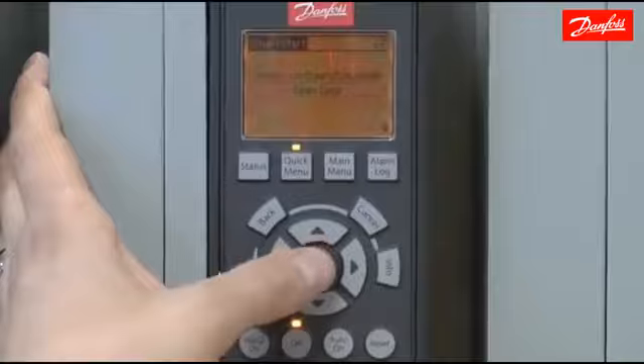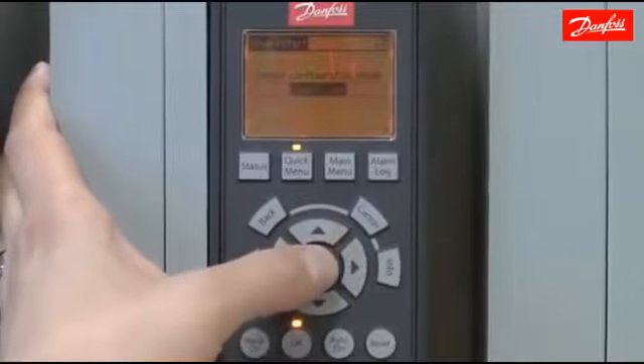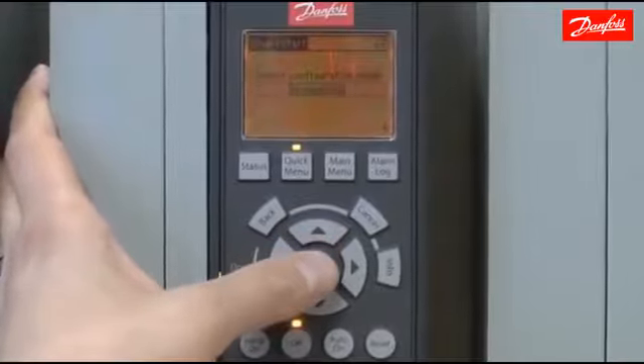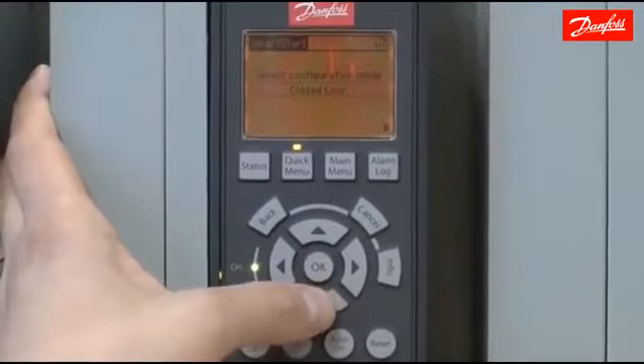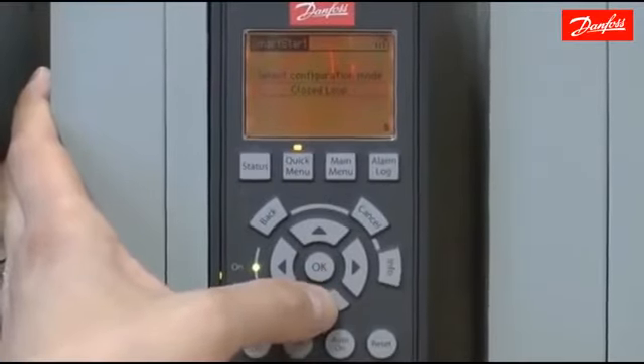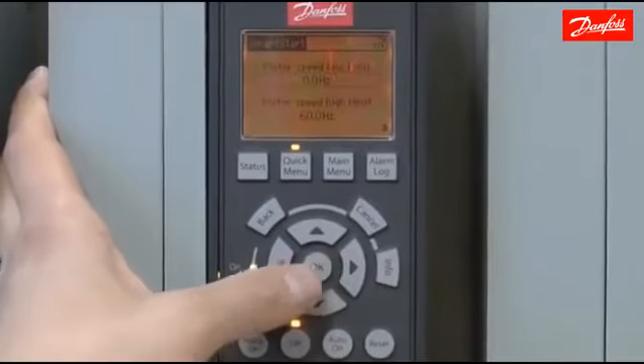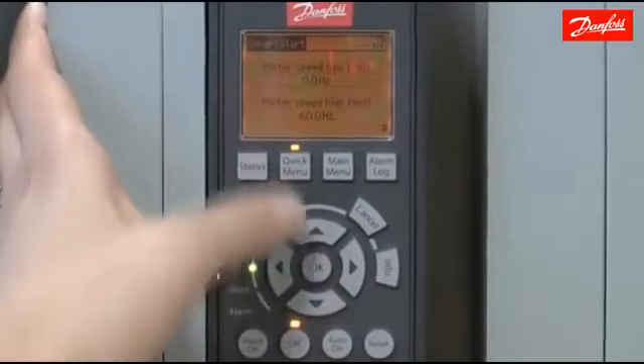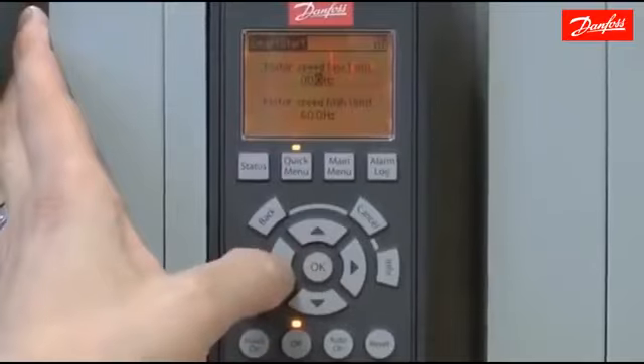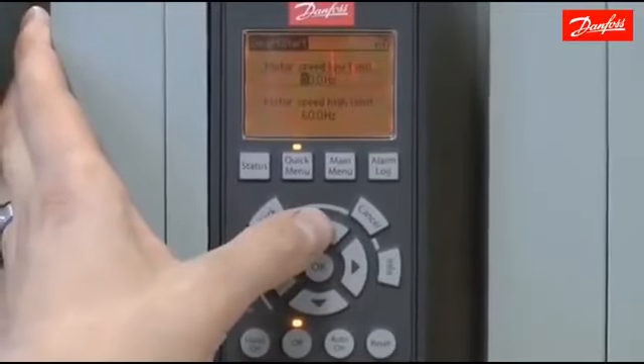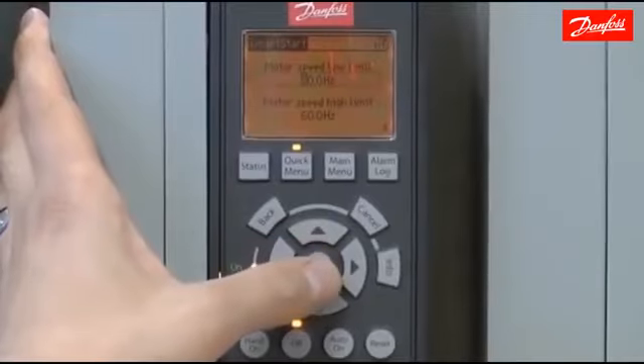We're going to choose the single pump or motor since that's what's involved in our application. The configuration mode, we're going to choose closed loop because we want to use pressure transducer feedback. So closed loop for the configuration mode. Moving on, I'm going to choose the motor low and high speed limit.